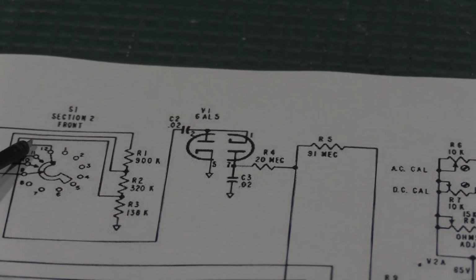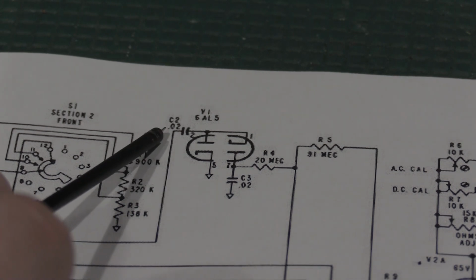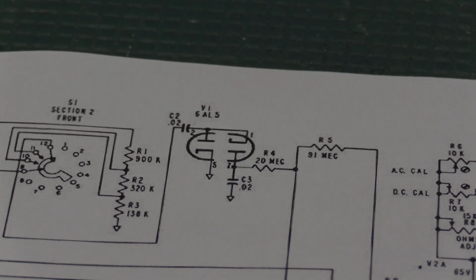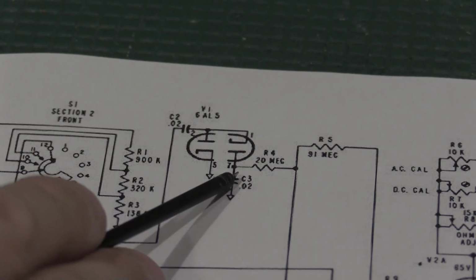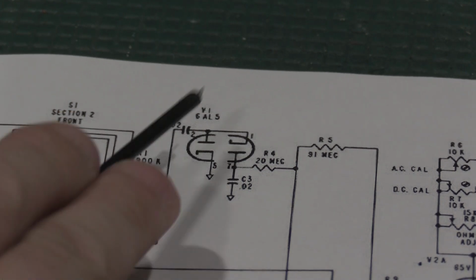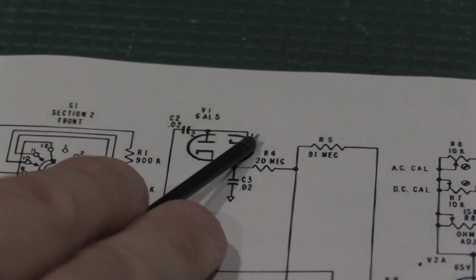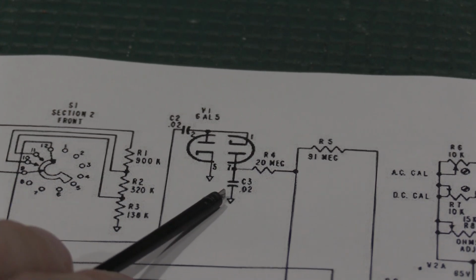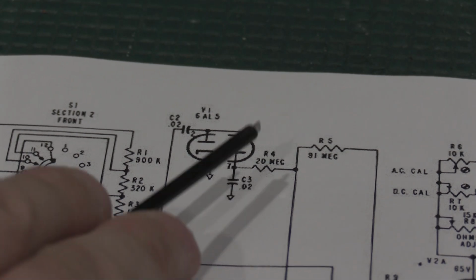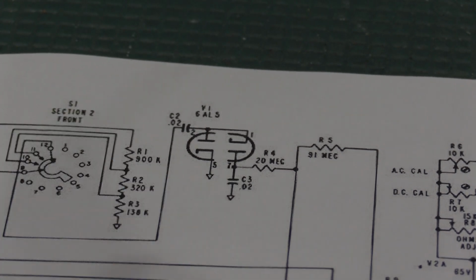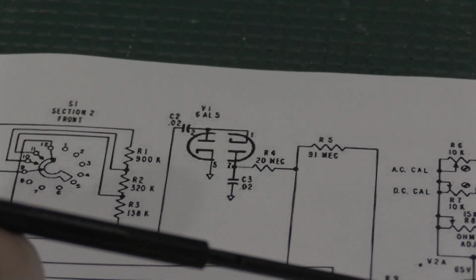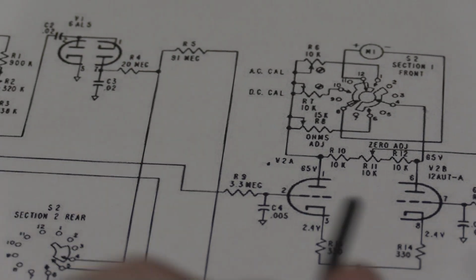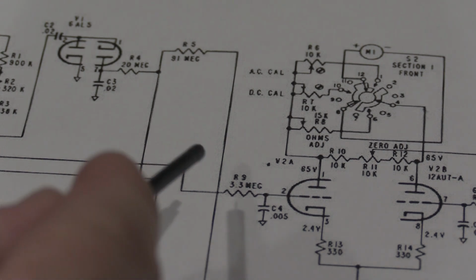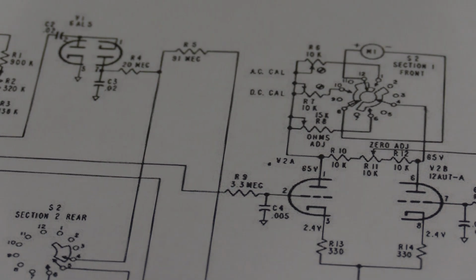Our AC signal actually pops out here at switch pin 12 and then couples through this capacitor into this rectifier. It then comes out of the rectifier from this side of the plate here, so it goes into the first plate, cathode's grounded, but it also goes into plate and cathode, and then this one comes out. This cap seemed to be okay. This resistor was bad as well, so it was this capacitor and this resistor that was causing the AC range to be off, and then that goes into the grid of the, let's see, after going through some more attenuators, it comes back to the grid of the 12AU7 to get into the DC amplifier, but it's DC at this point.